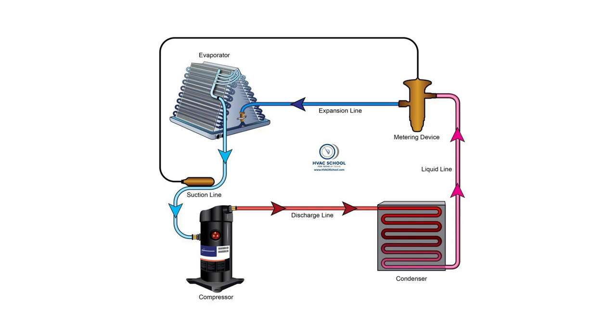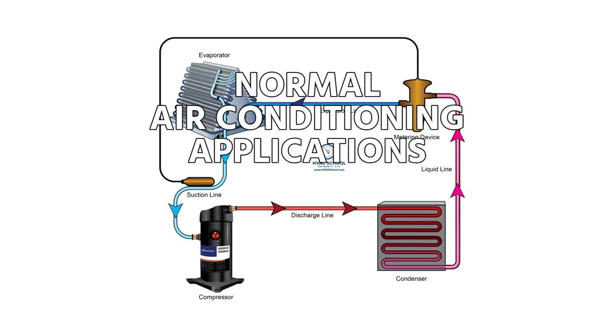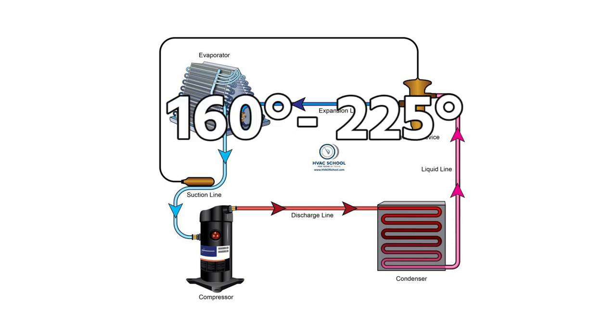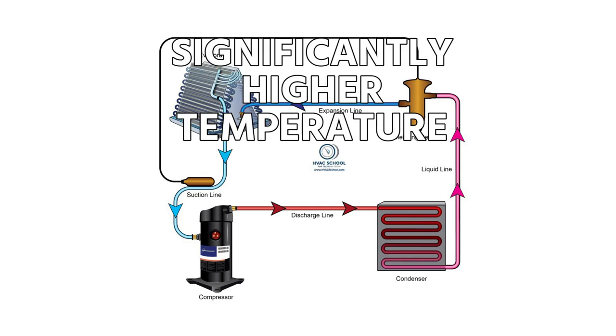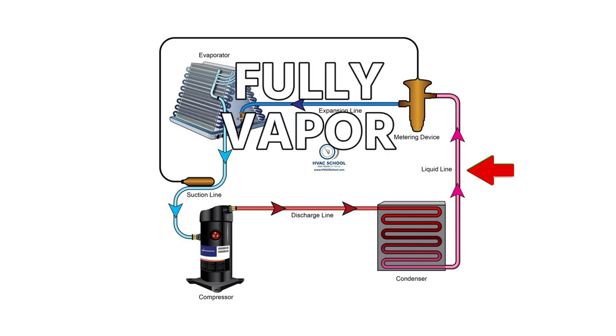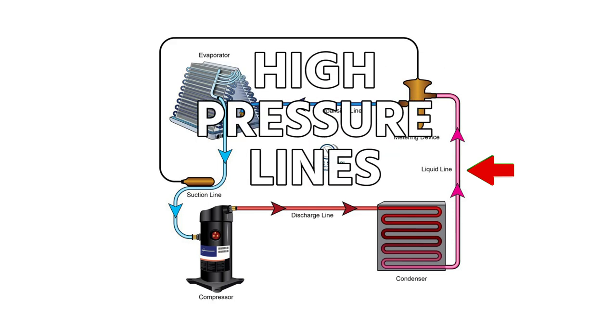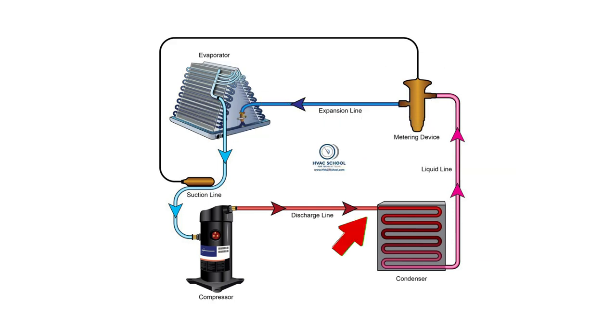Generally speaking, in most normal air conditioning applications, it's going to be somewhere between 160 and 225 degrees, and generally going to be closer to that 160 degree mark. But it's going to be significantly higher temperature than your liquid line and it's going to be fully vapor. So though they are both high pressure lines, one is going into the condenser and one is going out of the condenser.